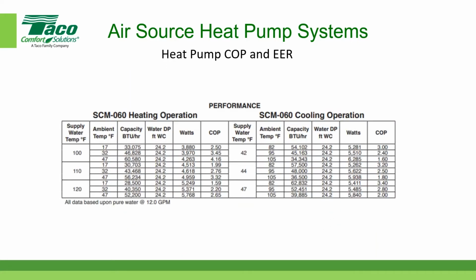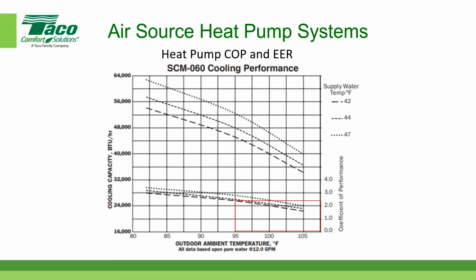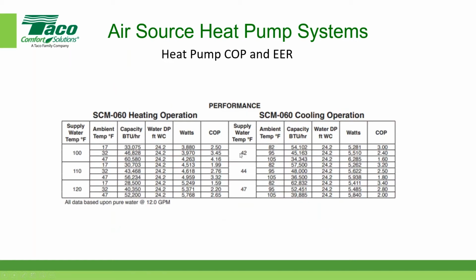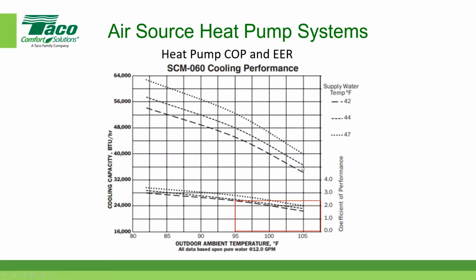Okay, let me just go back here. Now let's look at what happens to the same information that we just looked at. This was the cooling capacity. We're making 42-degree water with a 95-degree ambient air temperature. If we look at that on a graph, the capacity is in the upper half of the graph over here, for 42-degree Fahrenheit water with 95-degree ambient temperature. Follow 95 up to where it intersects this dotted line here.